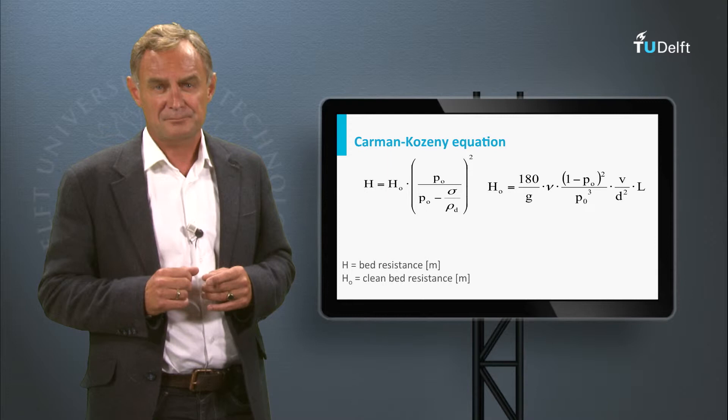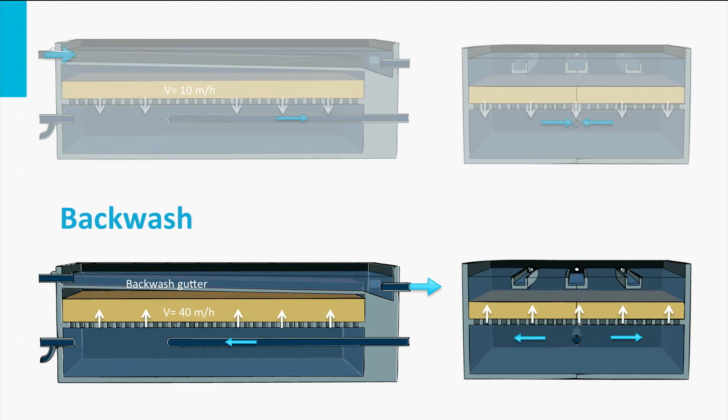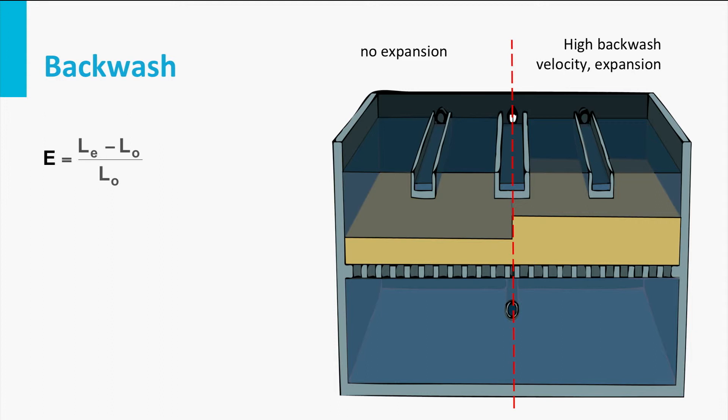When the filter is clogged, it must be backwashed to remove accumulated solids. This is done by briefly reversing the flow at a high enough rate that the bed becomes fluidized. Bed expansions of up to 20% can be reached. Extra air is often used to scrub the filter grains for more efficient washing. Bed expansion is an important parameter for designing a backwash facility, and the porosity during expansion can be calculated when the initial porosity and bed heights during filtration and backwashing are known.